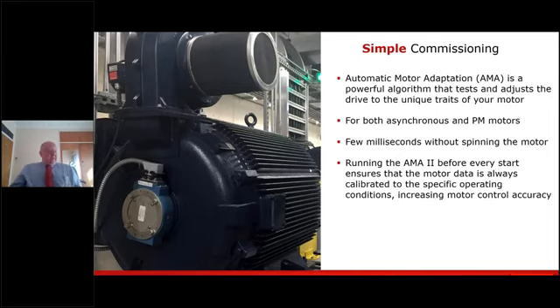So, assuming that this auto tuning improves the overall efficiency, let's say the VSD and the motor combined, and if it's just, let's say conservatively, by just 1%, based on the typical load profile, the reduction in the operating cost as a result of this improved efficiency equates to approximately 2 to 5% of the VSD. And remember, that's year after year after year.